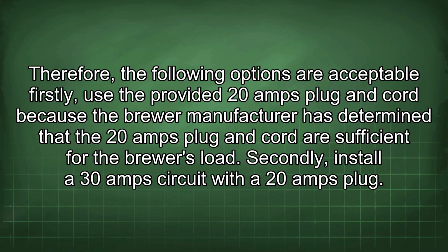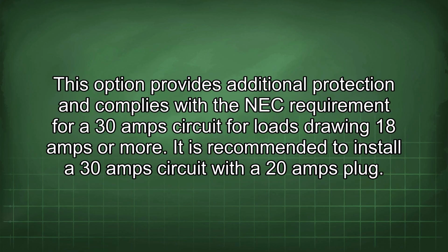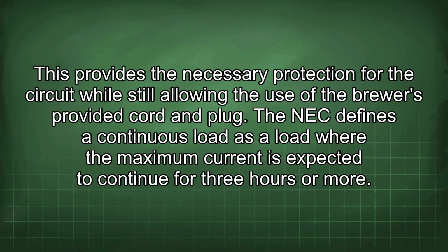Secondly, install a 30 amp circuit with a 20 amps plug. This option provides additional protection and complies with the NEC requirement for a 30 amp circuit for loads drawing 18 amps or more. It is recommended to install a 30 amp circuit with a 20 amps plug. This provides the necessary protection for the circuit while still allowing the use of the brewer's provided cord and plug.